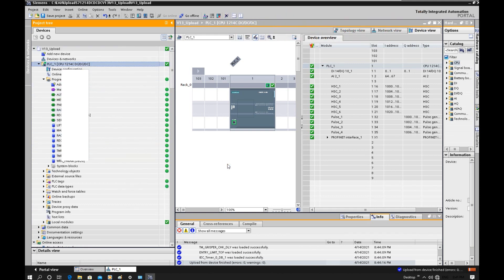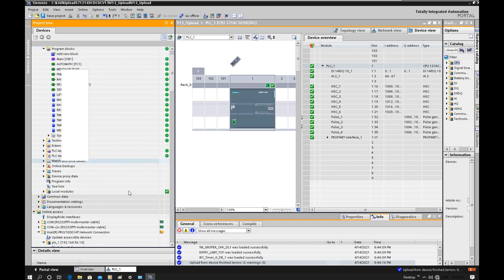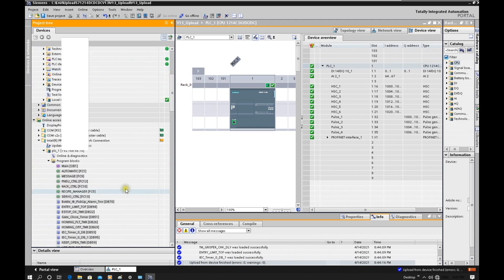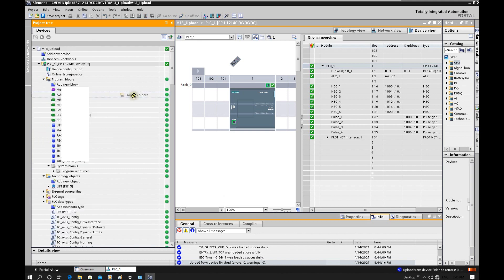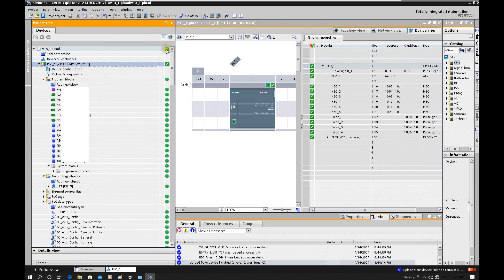I want to mention one thing for TIA Portal version 11. Because that is the very initial version, it is a little bit different. For TIA Portal version 11 you need to drag the online program blocks over the offline project blocks. But after TIA Portal version 12, you simply go online with the PLC, highlight the project, and then click Upload from device to upload the PLC program.